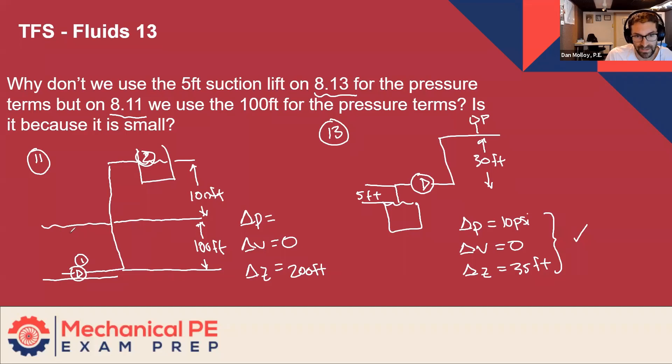So it's zero minus a hundred feet. Now you could turn that hundred feet into whatever the corresponding PSI is by dividing by 2.31, but we actually prefer to have it in feet anyway. And it is the column of water that's a hundred feet high. So I'll just keep it in feet. And I defined the static pressure then as minus 100 feet.